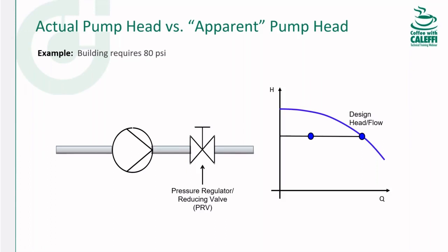When you're at low flow, which is going to be frequent on a booster, especially in a residential or commercial building, you're going to have pressure coming in from the city. This example might be 20 PSI coming in to the pump inlet. If you're looking at one of these PRV systems, you're going to see 80 PSI discharge, you're going to see 20 PSI suction, and you're going to see what I call the apparent head of a boost of 60 PSI. So that's about 140 feet of head. If you were to select a replacement booster, that's really all you need, maybe even a little less, but you want to size a replacement based on that same apparent pump head.